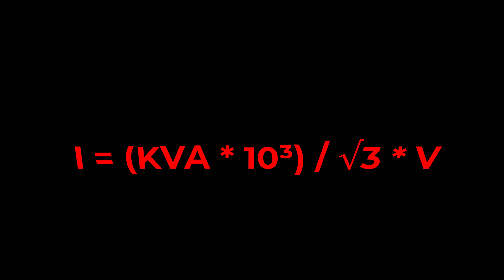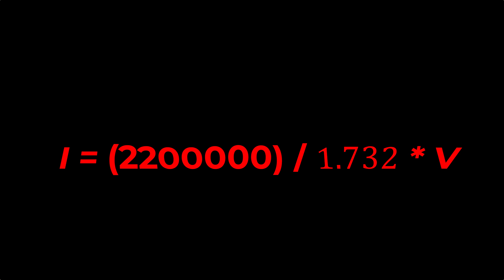We will calculate from 2.2 MVA to VA using the formula. Since KVA × 10³ = KVA in VA, for MVA we use MVA × 10⁶. So 2.2 MVA × 10⁶ = 2,200,000 VA. We then divide by √3 × V. √3 equals 1.732, and V is 11 KV, which we write as 11,000 V. The answer will be 115 A.